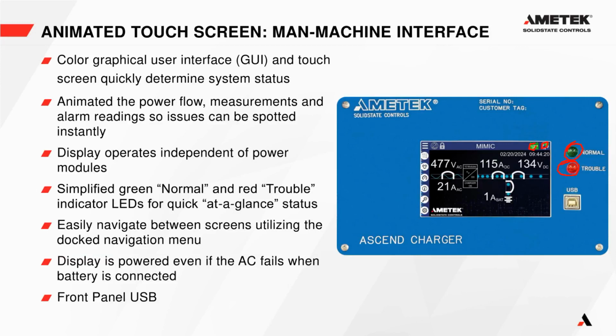The side menu over here allows for easy navigation between all of the screens on our system, and that's available on every screen when you're using the charger. And the other thing I said earlier is we have a front panel USB that allows you to connect our SCI Link software to download logs, alarm history logs, battery history logs, and get system statuses for the whole system and each module as well.